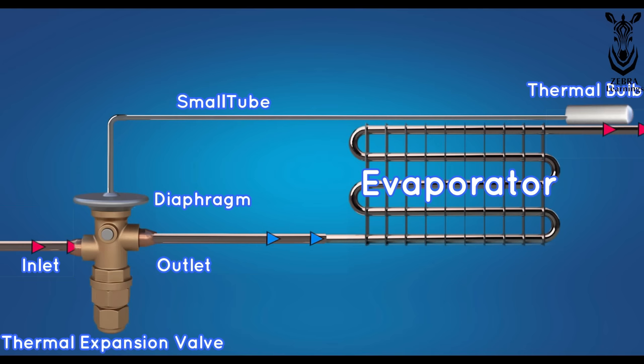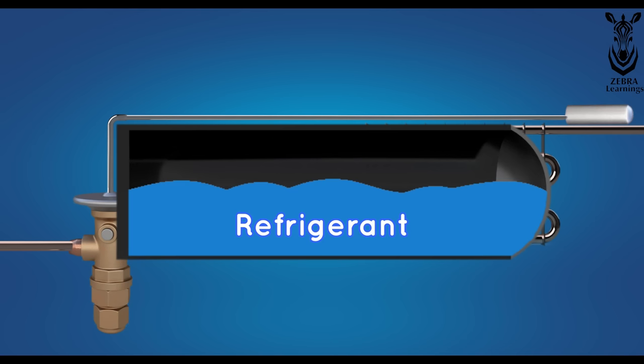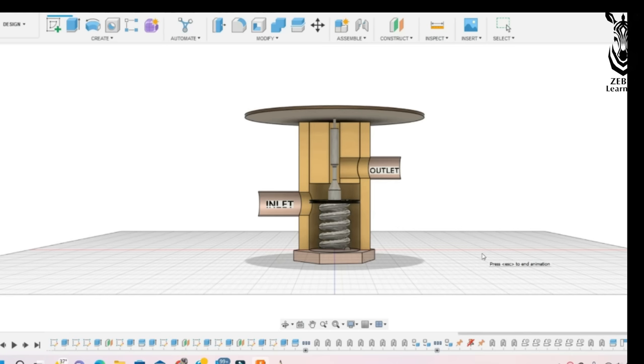Hence, the evaporator coil also cools down quickly. After the evaporator coil cools down, its outlet part also starts cooling down. So, the refrigerant inside the thermal bulb will stop boiling, and the pressure will be released in the diaphragm.